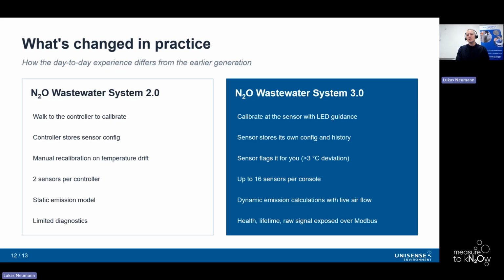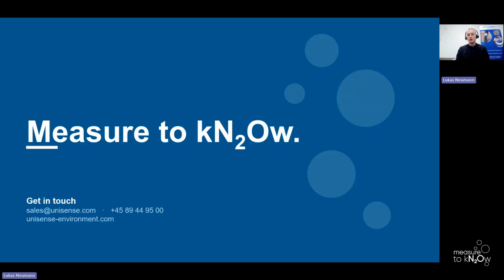In terms of emissions and emissions model calculations, previously this was based on static factors, whereas in the new generation, these are dynamic calculations using the plant's or that specific tank's live airflow data. In terms of diagnostics, previously it was a bit limited, and now with the new generation, we have the full health, lifetime, the raw signal, all exposed over the Modbus. So while the measurement principle is identical, and your data series stays comparable between the generations, we have just changed the workflow, and we're certain your operators will feel that from day one.